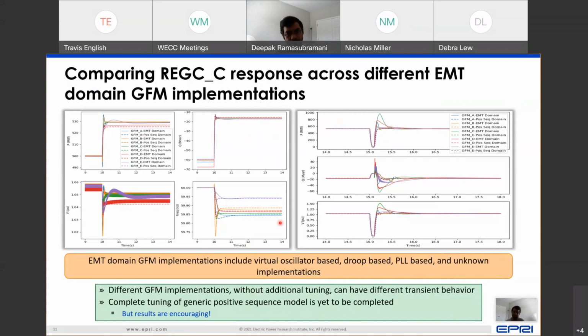Now, there was a question which a member from a WECC utility asked us a few months back: we have these new positive sequence models and all of that is very good, but can we really study something like a system islanding scenario in software like PSLF with these new models? Suppose there is an area or a zone of the system that needs to be isolated from the rest of the network for whatever reason, maybe a wildfire is coming through, maybe there's a tornado blowing across. There needs to be a portion of the system that is isolated from the rest of the network, and we want these two networks to continue to operate, but an islanding behavior has occurred. And the portion that islands is only inverters and nothing more. Can we study such a behavior with this REGC model?